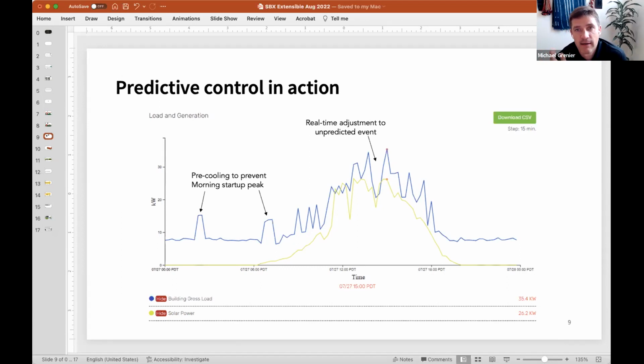What's happening is the software is predicting the cloud passing over the solar array, realizing it's going to set a spike, and quickly changing the dispatch of the HVAC system, typically by raising set points for a period of time until the solar comes back. So what looks like a big dip in the load profile, the blue line, would have actually been a really huge spike. That's what we call the biggest mistake of the month avoided.